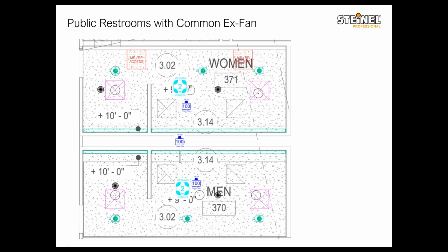Okay, so one other application that kind of fits in between is use of a COM2-24 sensor for control of an exhaust fan or a ceiling fan in the case of offices. So let's say you have a public restroom, and in this case we have a men and women public restroom with a common exhaust fan. So we want to make sure that based on occupancy on either side, the common exhaust fan would be turned on.